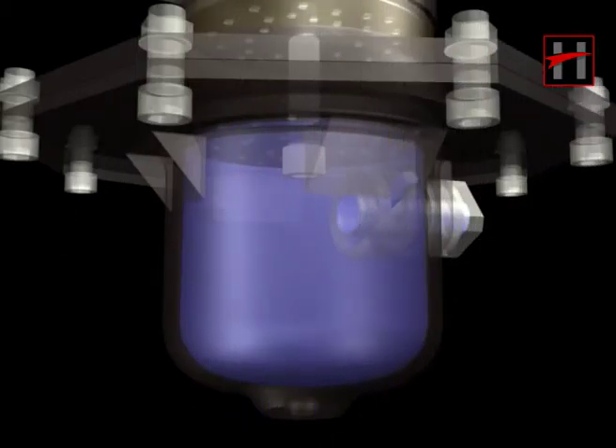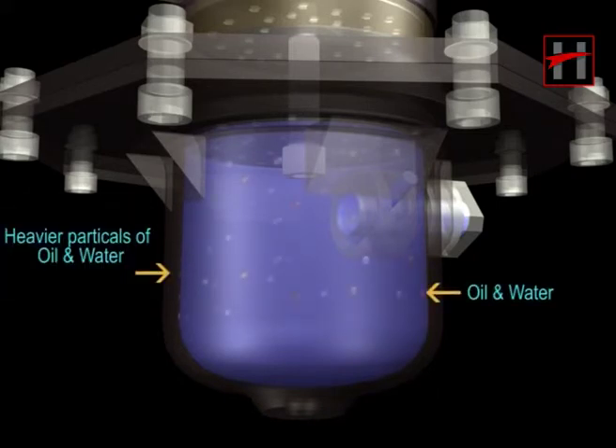The centrifugal force developing in the swirl ring and on the container wall expels the heavier particles, such as droplets of oil and water, from the compressed air and deposits them on the inside of the container where they run down into the collecting chamber.